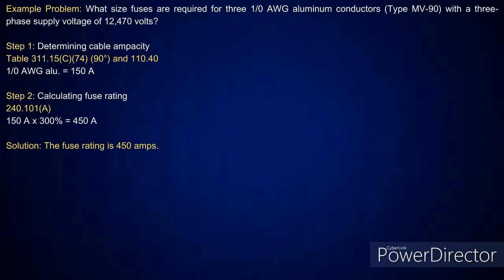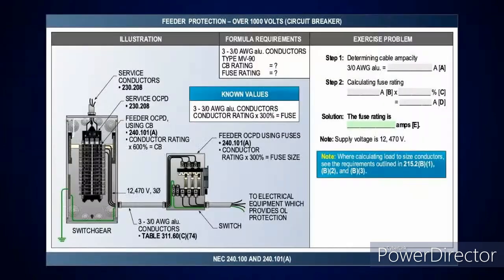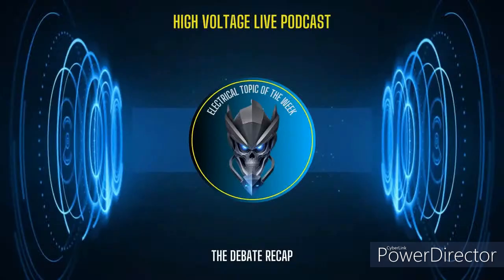All right. And then here's your fuse rating. It's the exact same question. The only difference is, if I have a circuit breaker rating, it tells me to take it at 600%. But for a fuse rating, it tells me to take it at 300%. And it'll tell you here that you take the 150 amps at 300%, and you'll have a fuse rating of 450 amps. Okay. Nice. And you'll notice here, I've got the exact same problem I had before. You're just going to do it at 300% instead of 600% to get that fuse rating size. All right.